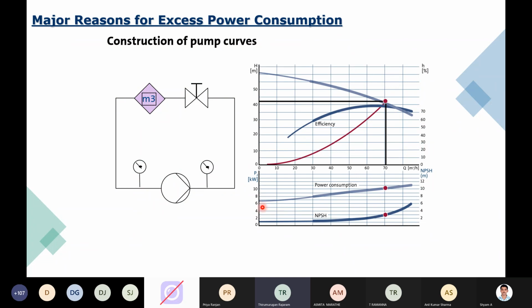And same, you have your power consumption on your y-axis and your NPSH. So NPSH is your net positive suction head that is required, a design value for any pump manufacturer. So in this case, the important thing is your power consumption. What you can see is that a pump is being designed to operate between, for example, 61 as your maximum head and your least head close to 33 meters. And same thing, your power condition also.